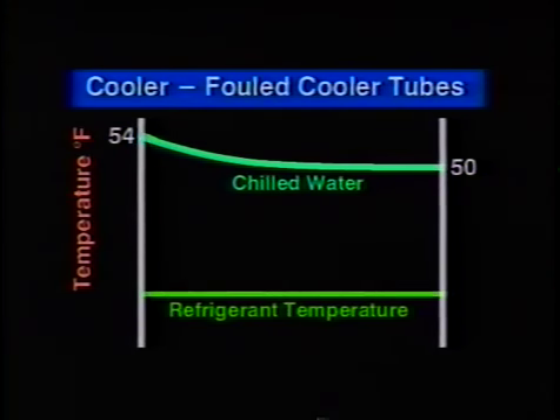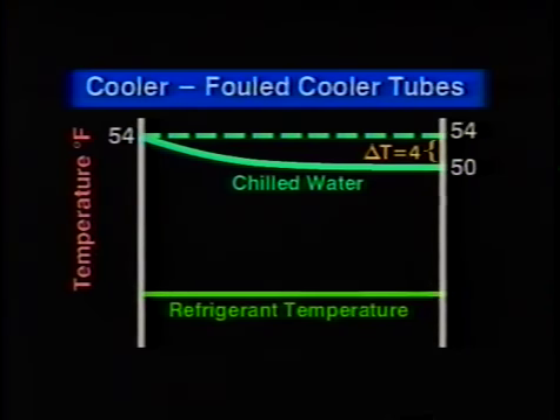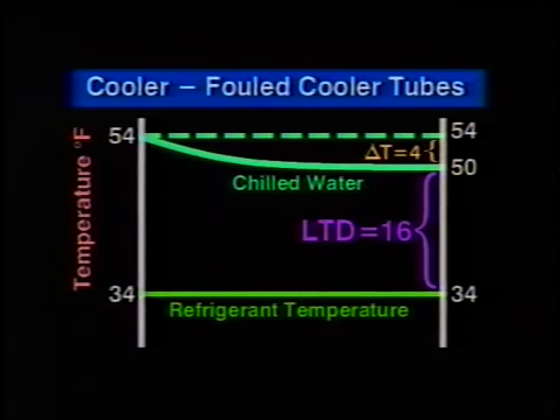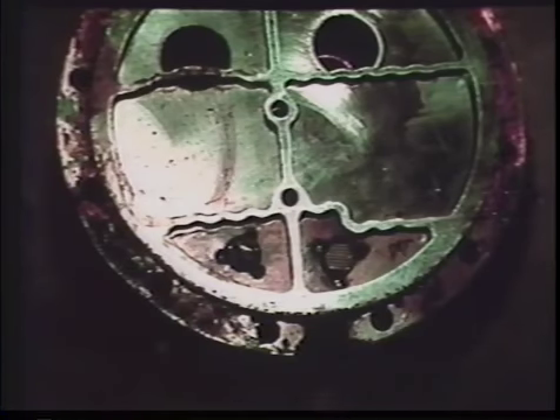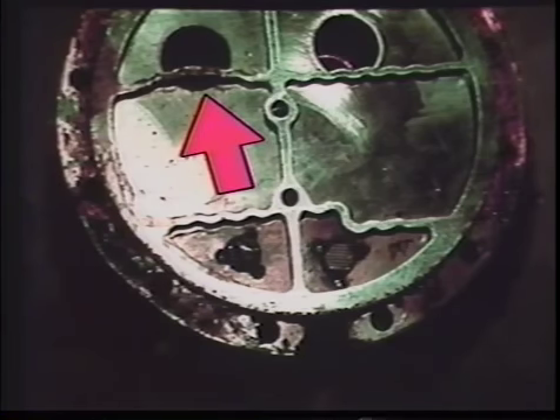Fouled cooler tubes can also cause an above normal approach curve because of the reduced heat transfer. Suppose we have a 4-degree Fahrenheit drop across the cooler with a low saturated cooler temperature of 34 degrees. The LTD is now 50 minus 34, or 16 degrees Fahrenheit. This confirms that the heat transfer has slowed. The delta T and LTD trends are the same as a low refrigerant charge, but a check on suction superheat shows that it's at or near design. In this case, the problem would likely be fouled cooler tubes. However, a refrigerant pass-to-pass leak caused by the failure of a cooler pass partition plate or gasket can give the same symptoms, usually on one circuit only. This should be checked out if the cooler tubes prove to be okay.